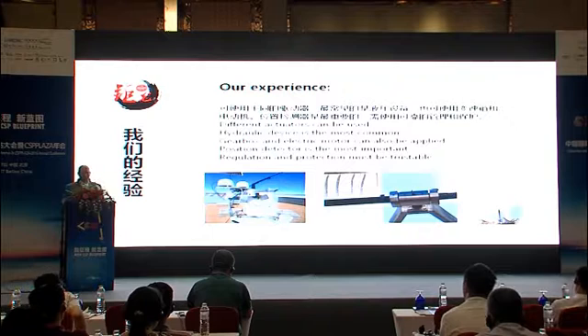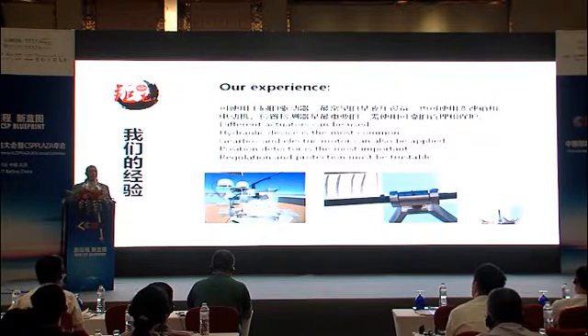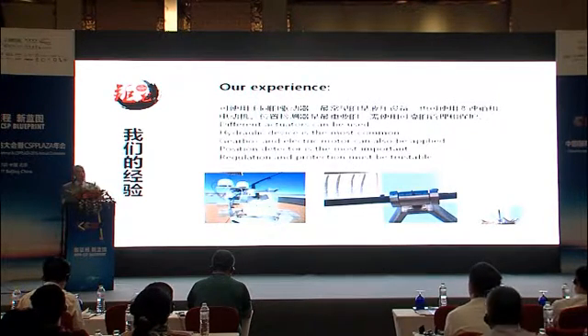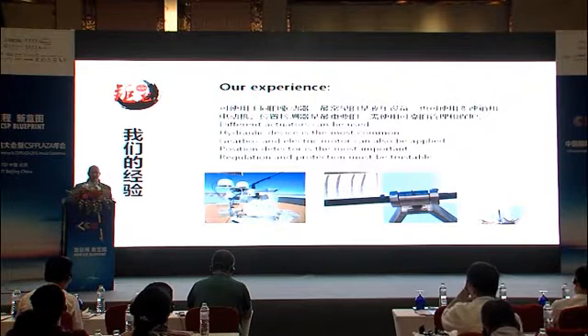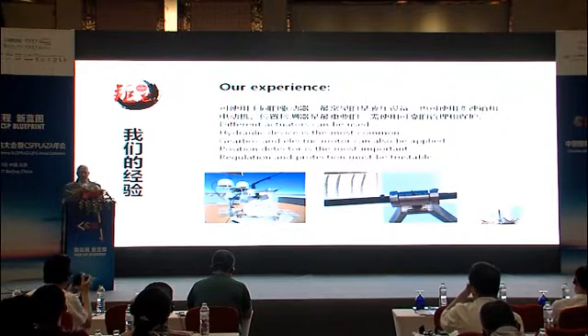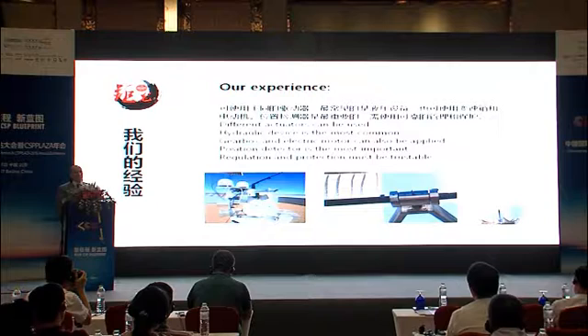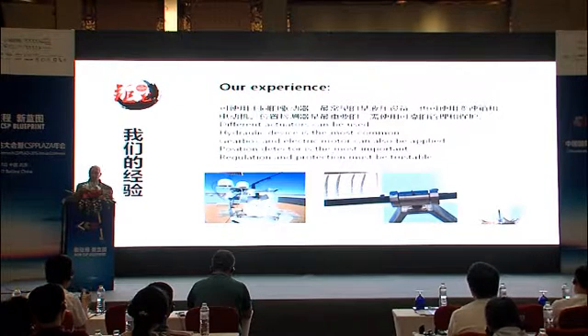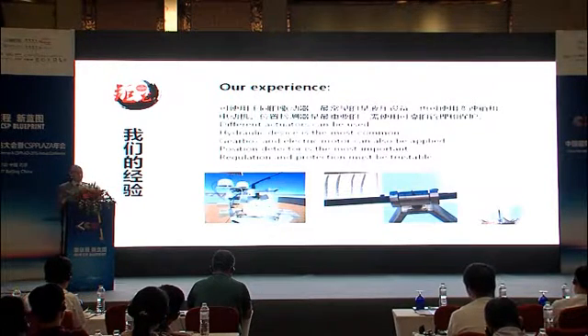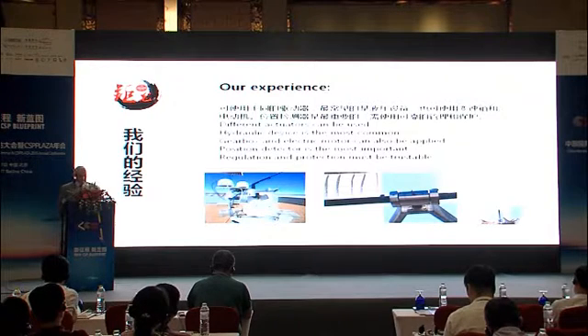Furthermore, in hydraulic devices you have the oil tank, filter, high pressure pump, motor, solenoid valves, flexible hoses, connections, two cylinders. I think we have so many chances to have a failure, and in fact they happen.